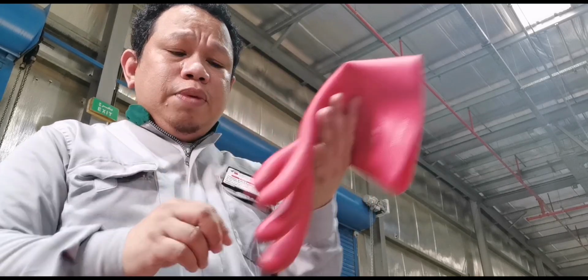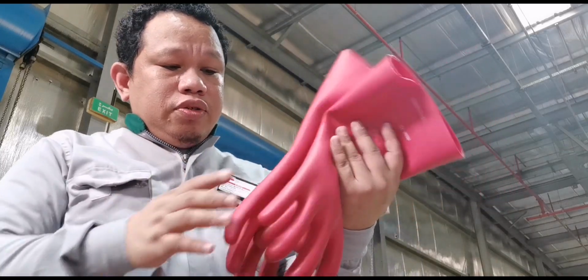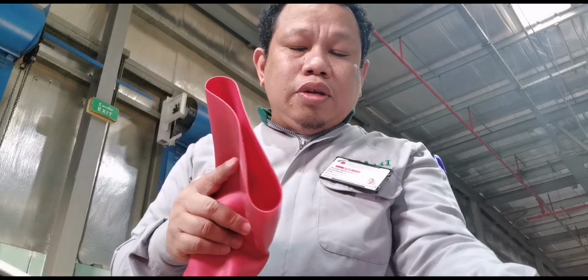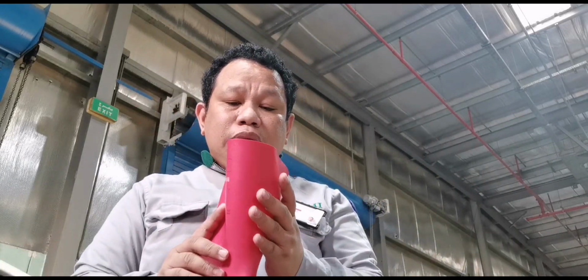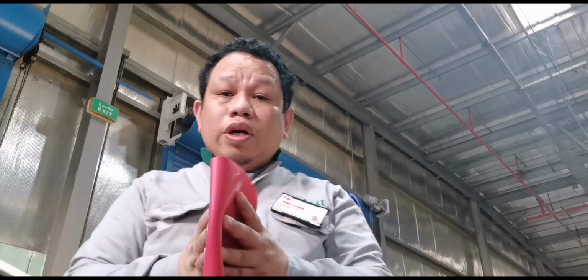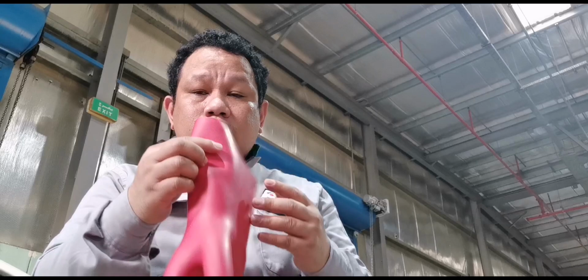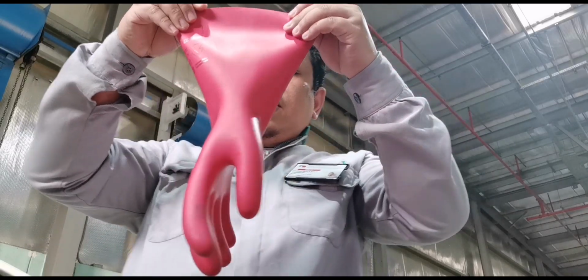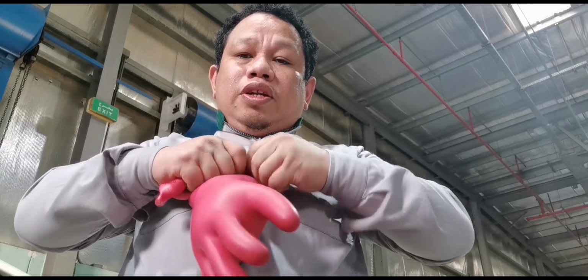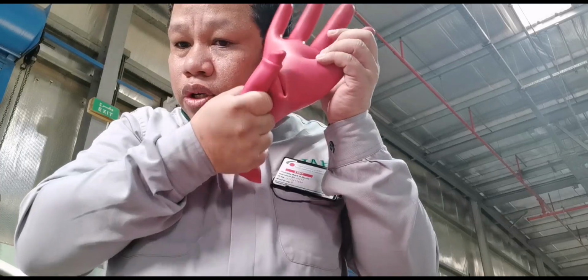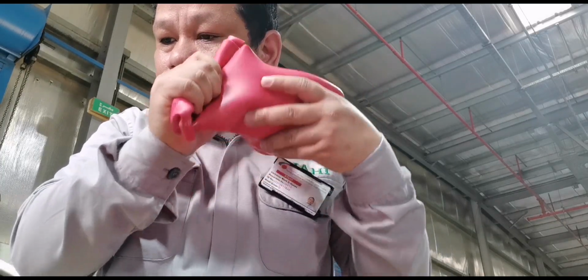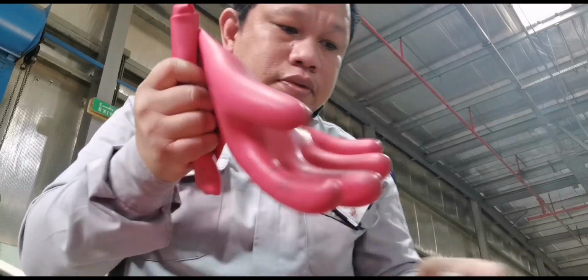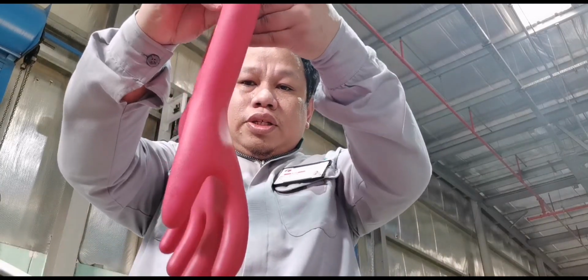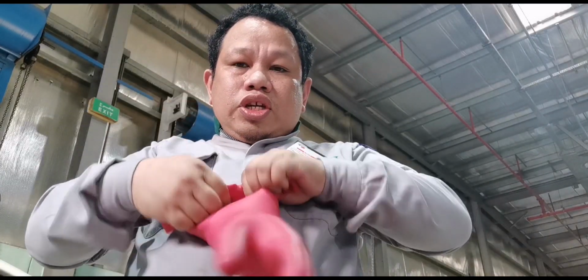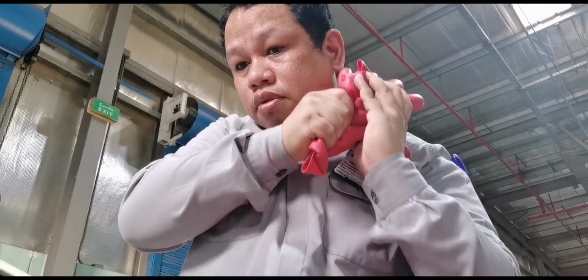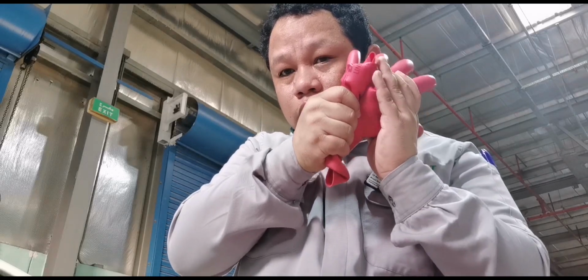So how do you check the gloves before wearing them? See to it that there is no damage, do a visual inspection, since even small damage may lead to an injury. All you have to do is roll it to one side like this, then fold it until air is trapped inside the glove, and try to feel if there is any leaking. If there is leaking, do not use the gloves. Do it on this side too, fold the upper portion, then check again for leaking. Okay, there is no leaking, so now it is safe to use the gloves.